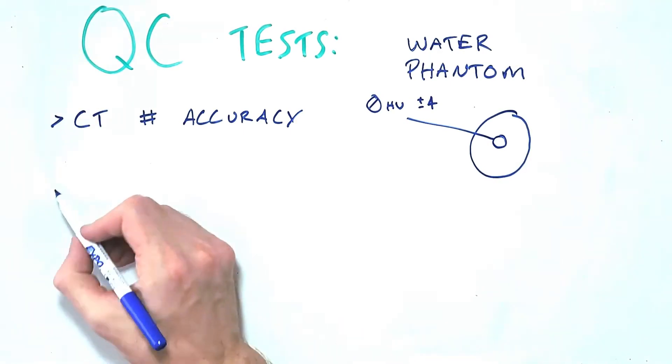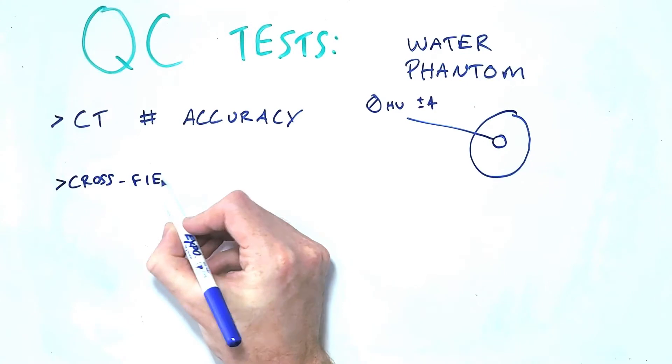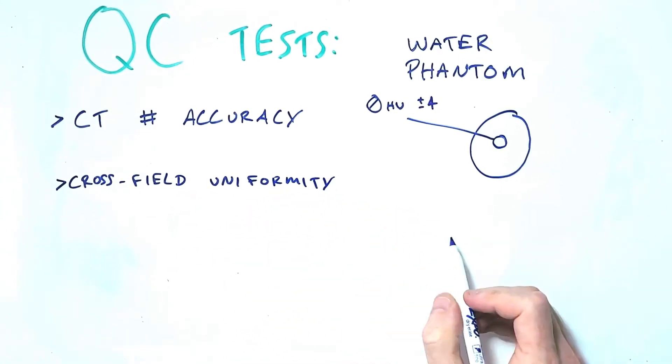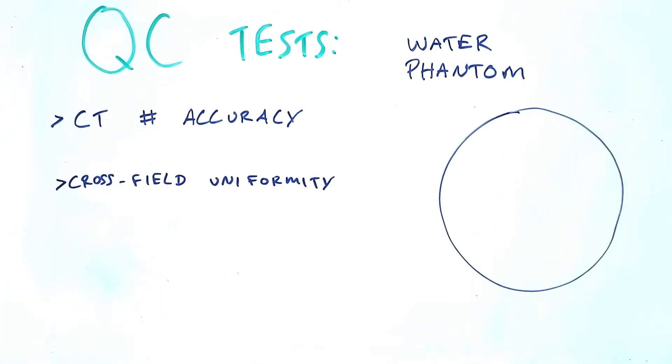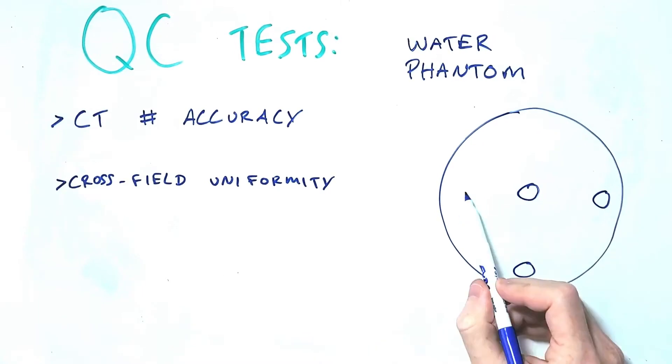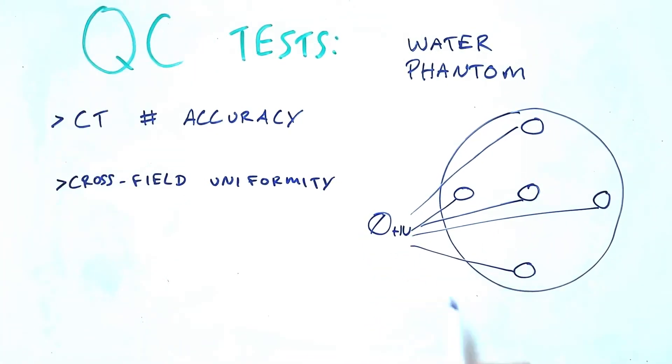When scanning this plain water phantom we can also assess cross-field uniformity and noise in a CT image. Cross-field uniformity is an assessment of whether the CT number of a homogeneous material like water is measured the same at the center as it is at the periphery of the phantom. In CT it's measured by placing one region of interest or ROI at the center of the phantom and then four ROIs around the edges of the phantom. The difference between the center and any of the peripheral measurements should not vary significantly from the baseline amount of variation established for each scanner.